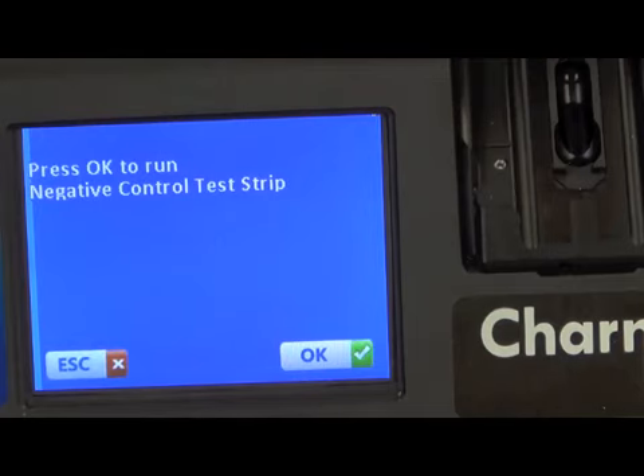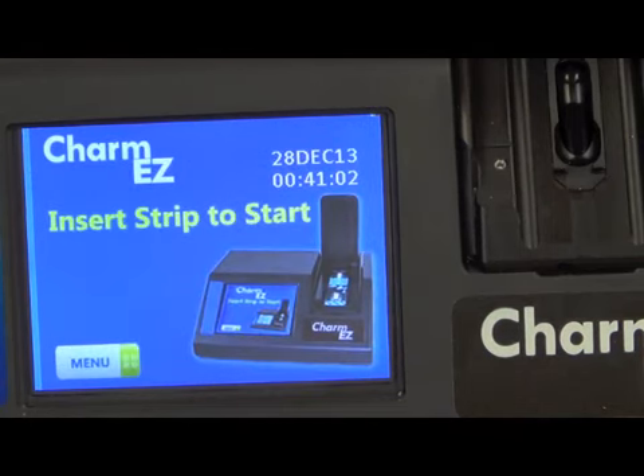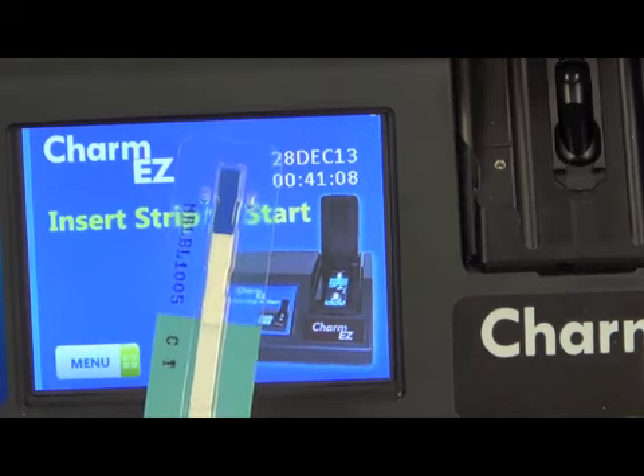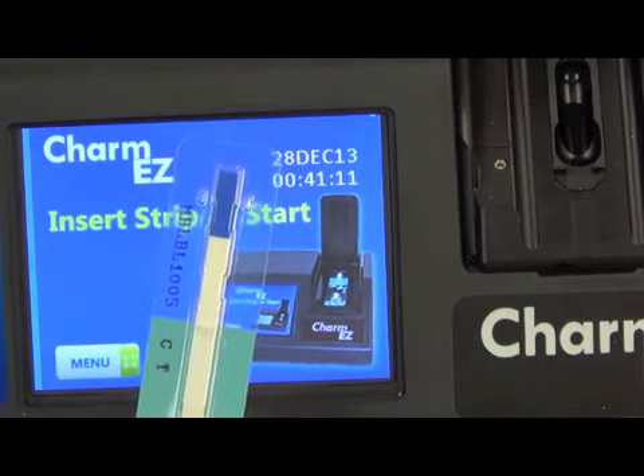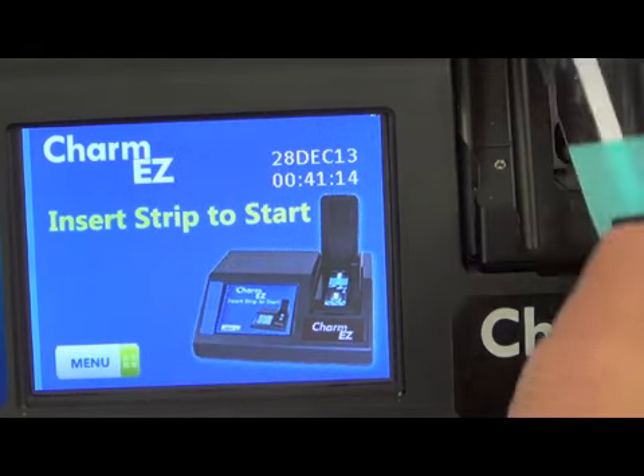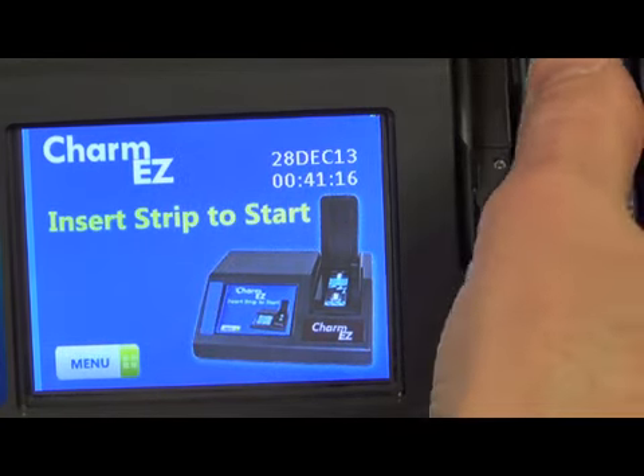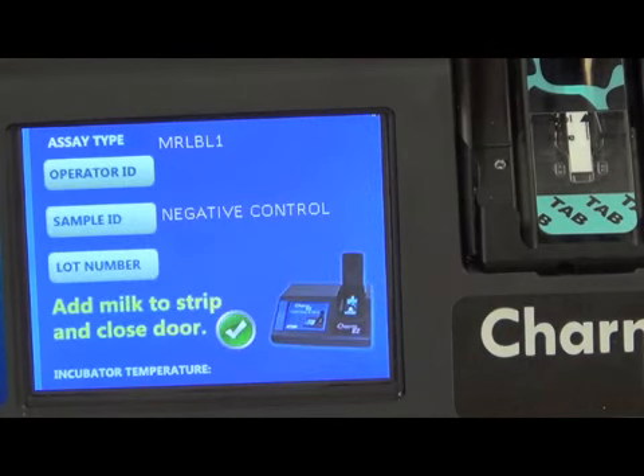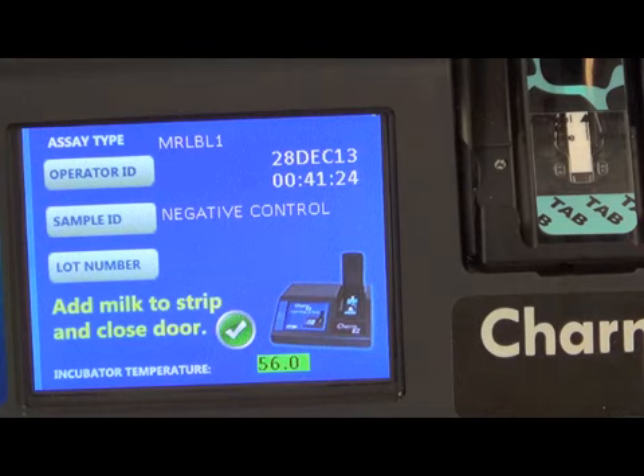The next prompt is it's going to ask to run the negative control. In this case, we hit OK. It's going to ask to insert the strip. We're going to run the MRL-BL1 test, which is our blue, easy color-coded ROSA test. Insert the strip into the reader. The reader will load the proper calibration values and also set the appropriate temperature. Again, in order to make sure that the temperature is correct, you need to wait until the temperature indicator is green, indicating that the test is in the proper range.